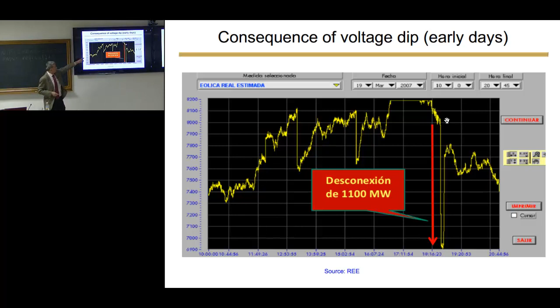This was in the early days, but it continued to be a problem. For instance, in Australia, there was a very huge blackout in South Australia affecting nearly 2 million people owing to voltage dips, because there were many thunderstorms and tornadoes that brought down high voltage poles, and each time this caused a voltage dip, a short circuit. So there were quite a few consecutive short circuits, and those short circuits were detected by the wind farms.